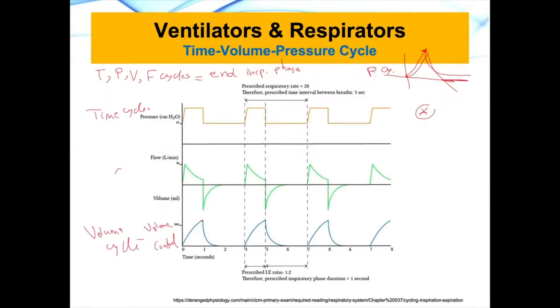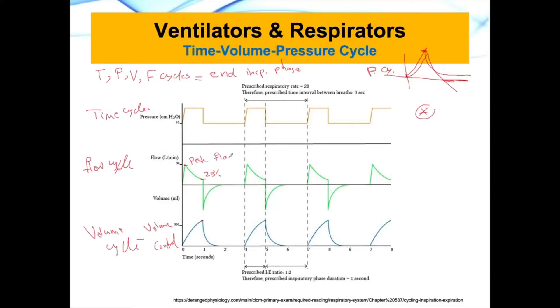The last cycle I would like to explain is flow cycle, and that is the green line here in the middle. In the flow cycle, you are asking the ventilator to increase the flow of gas in the patient. After a certain point, the flow will start slowing down — instead of increasing, it will start decreasing because there is resistance. Because there is air already inside the lungs, the flow will start getting smaller and smaller. If you reach, let's say, 25% of the peak flow, we are setting the ventilator that if you reach 25% of peak flow, close the valves of the inspiratory phase and allow the patient to exhale.